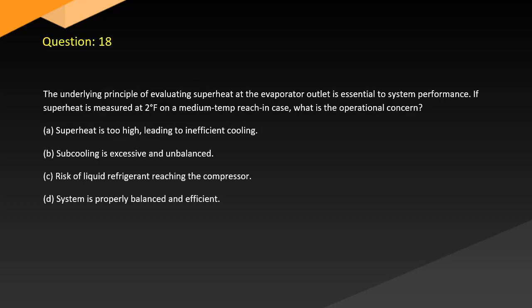Question 18. The underlying principle of evaluating superheat at the evaporator outlet is essential to system performance. If superheat is measured at 2 degrees from a medium temp reach-in case, what is the operational concern? A. Superheat is too high, leading to inefficient cooling. B. Subcooling is excessive and unbalanced. C. Risk of liquid refrigerant reaching the compressor. D. System is properly balanced and efficient.